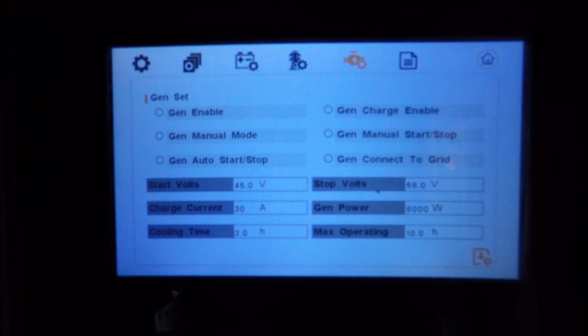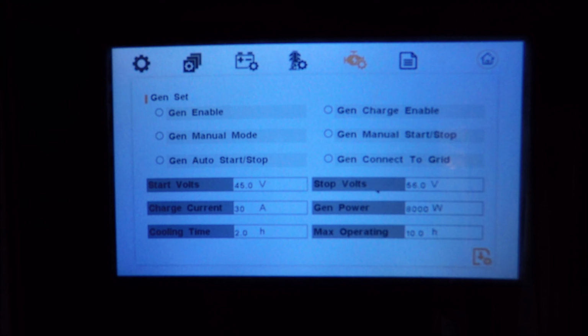Most common 240 volt generators in the United States are 5,500 watts. If you divide 5,500 watts by 240 volts, you will get 22.9 amps. You also need to take into consideration conversion losses, and you don't want to run the generator at its max. So for a 5,500 watt generator, you would set this to approximately 18 amps. For a 3,000 watt generator, it would be about 10 amps. For a 9,000 watt generator, it would be about 30 amps. So make sure that the charge current you set here to charge your batteries matches the output of the generator.